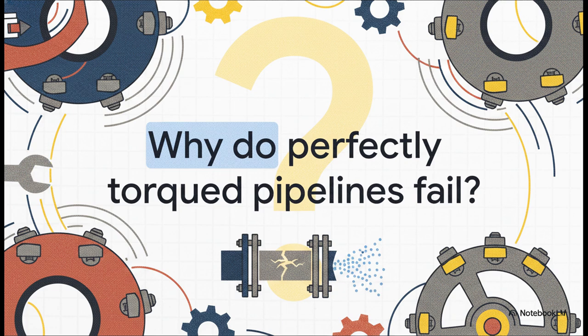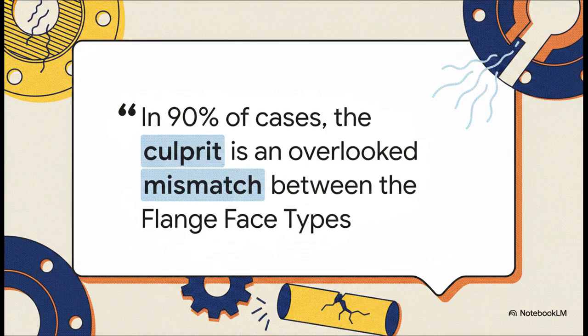Picture this. You're on the final stage of commissioning a high-pressure steam line. Your bolts are torqued to the exact spec, the gasket is brand new, the hardware is absolutely top tier, yet the joint fails. Why does mechanical tightness sometimes fall short of preventing a disaster? So the crucial point here is that in 90% of cases, the true culprit isn't the bolting or the pipe material itself. It's an overlooked mismatch at the sealing surface. Just a single microscopic scratch crossing the serrations or using the wrong face geometry can turn what sounds like a slight hiss into a full-scale multi-million-dollar plant shutdown.